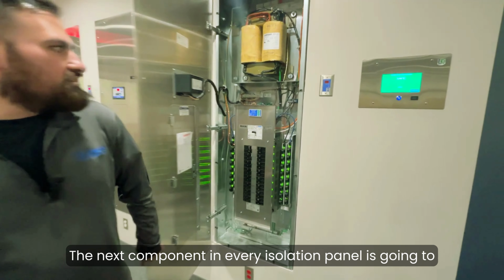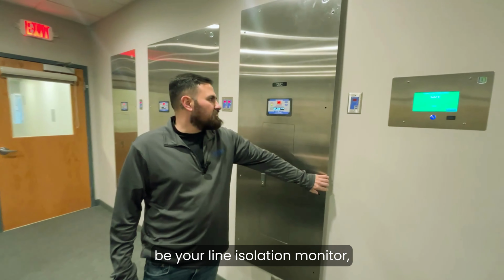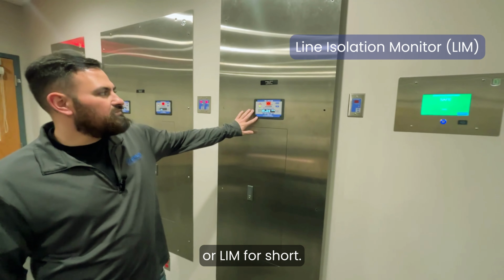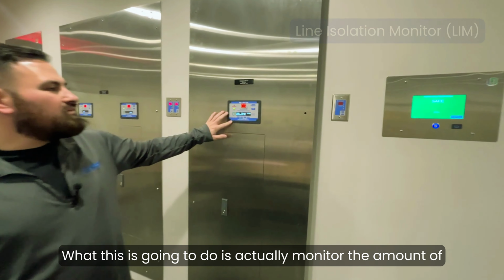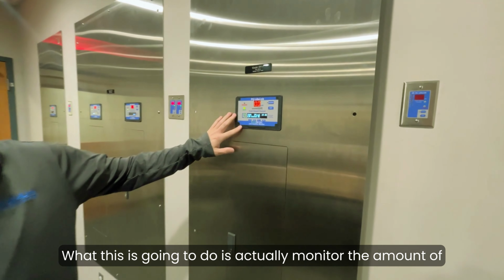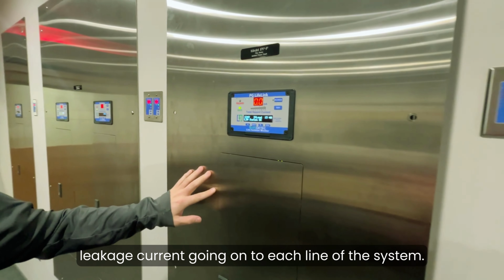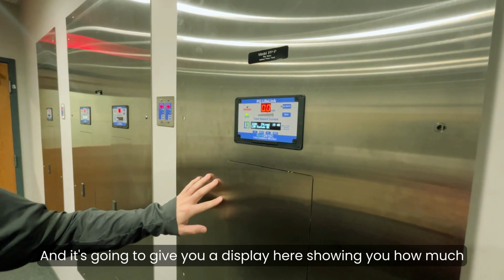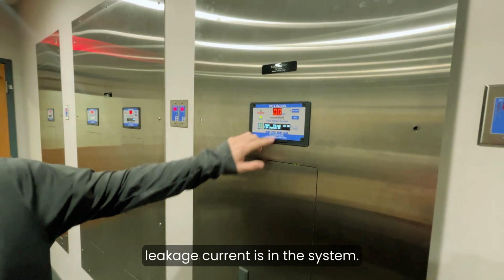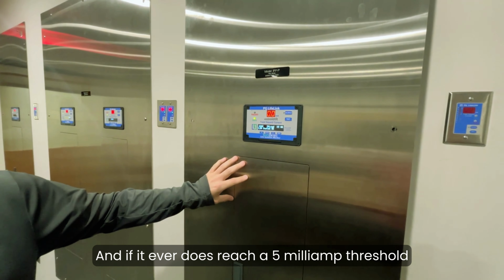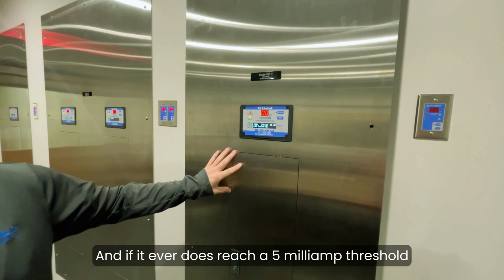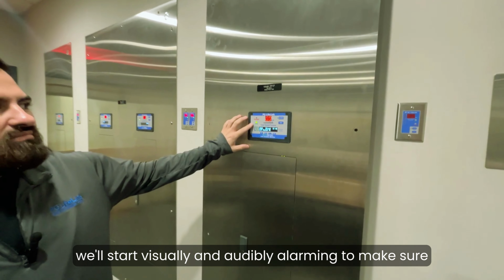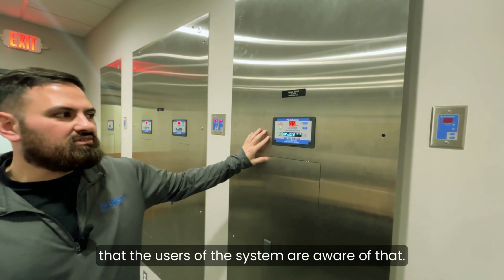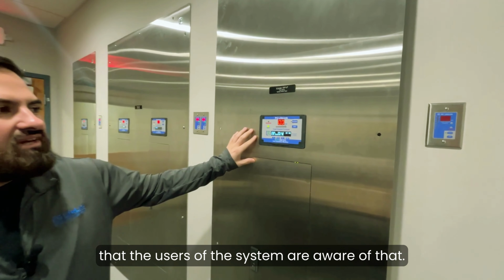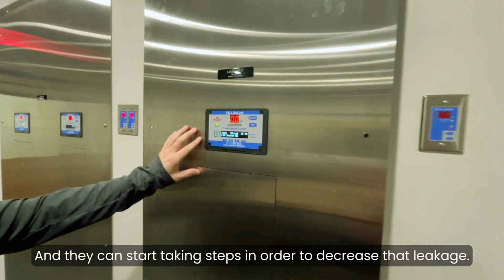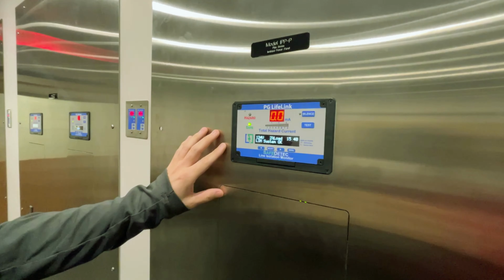The next component in every isolation panel is your line isolation monitor, or LIM for short. What this does is monitor the amount of leakage current going on to each line of the system, and it gives you a display showing how much leakage current is in the system. If it ever reaches the 5 milliamp threshold of injury, it will start visually and audibly alarming to make sure the users of the system are aware and can take steps to decrease that leakage.